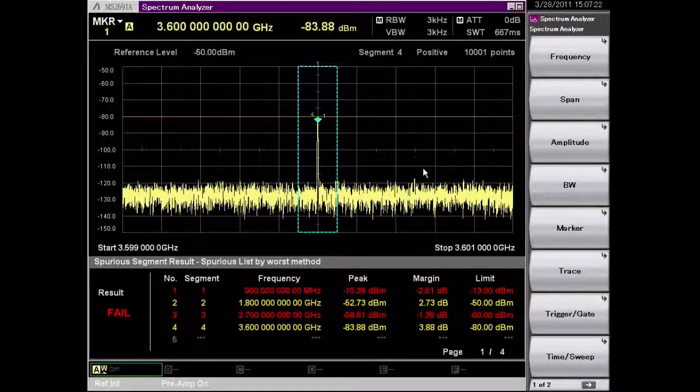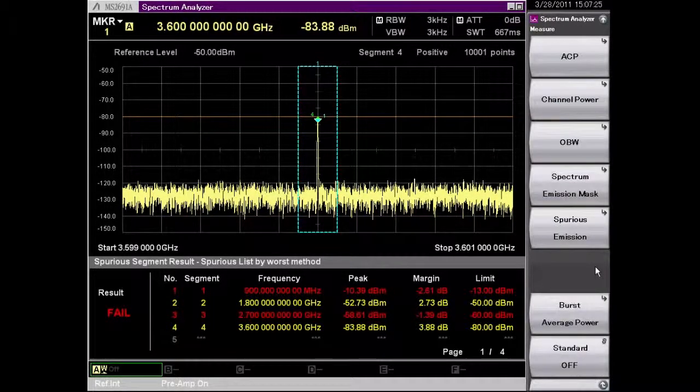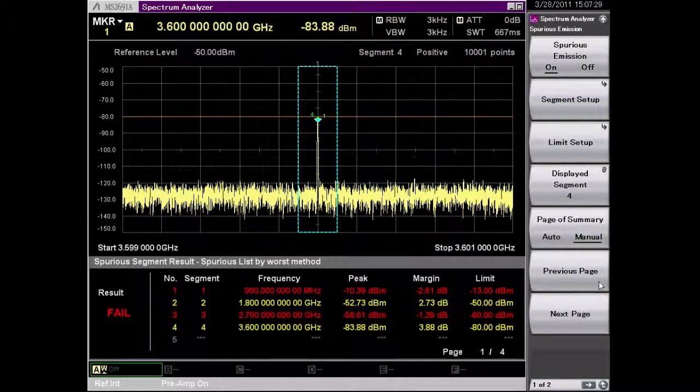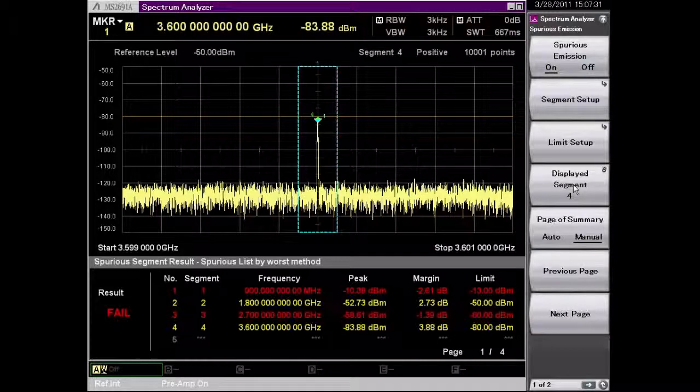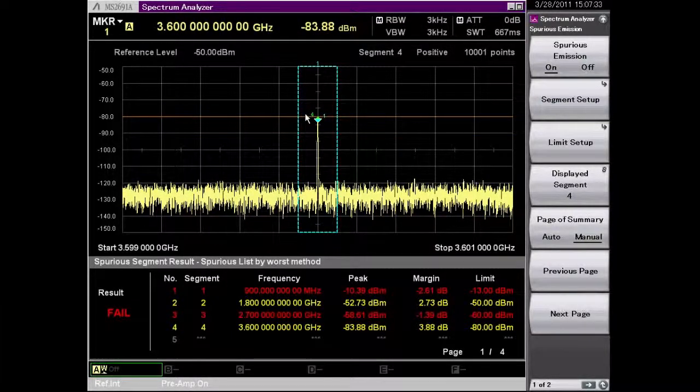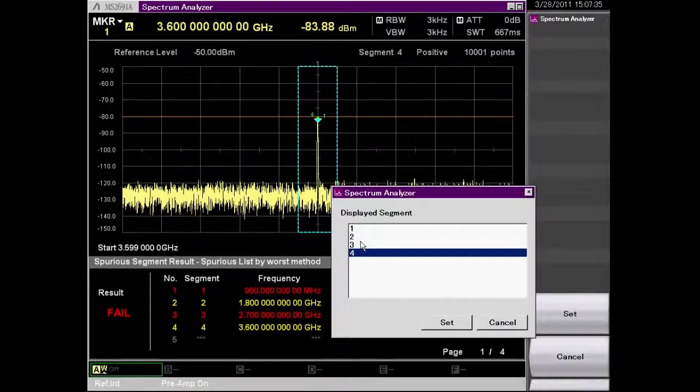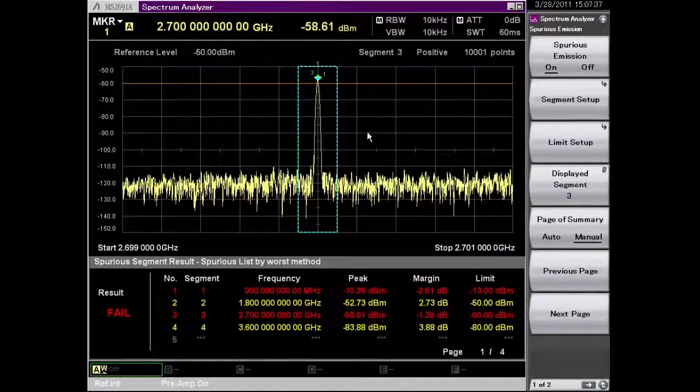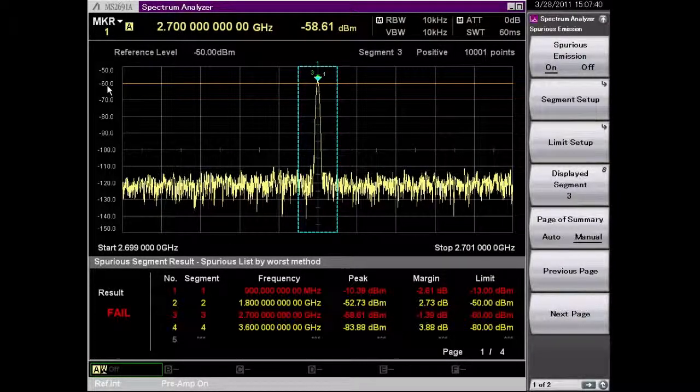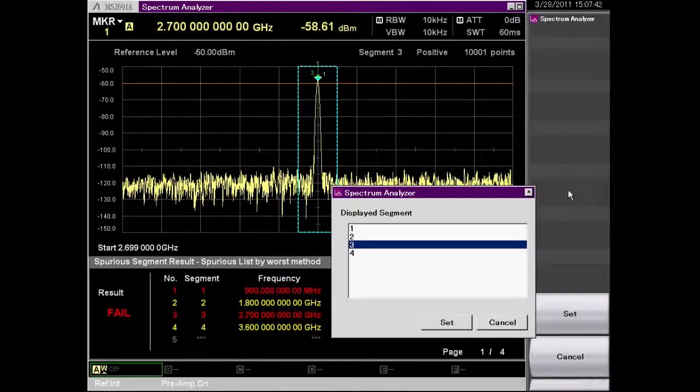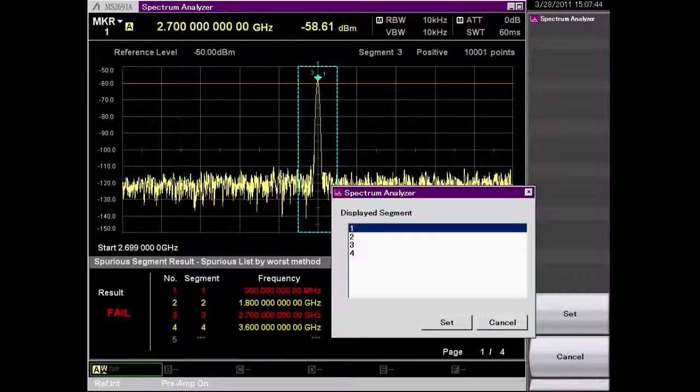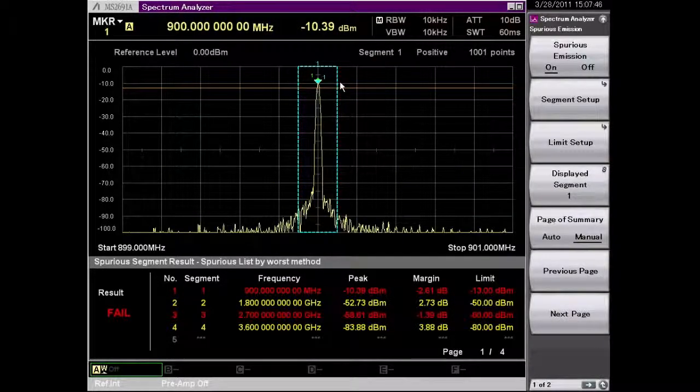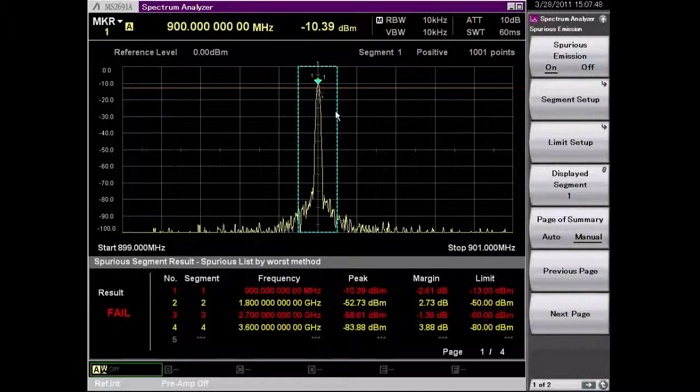So I can go in to measure and actually look at each one of those bands. Looking at segment 4 right now, I can change that to be segment 3. As you can see I'm just barely failing my limit of minus 60. Also look at segment 1. And here I'm failing my limit of minus 13.